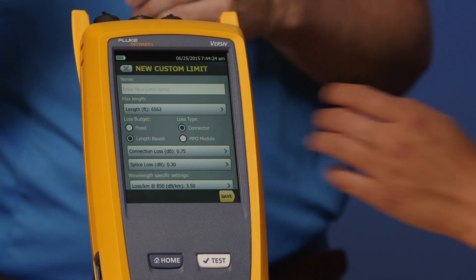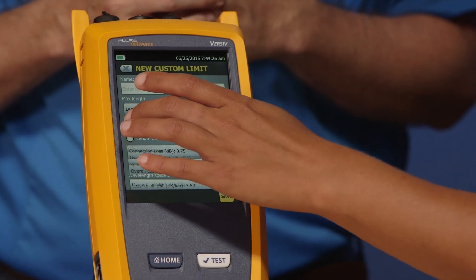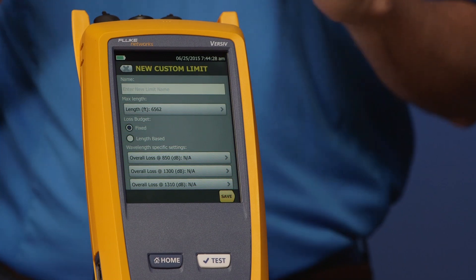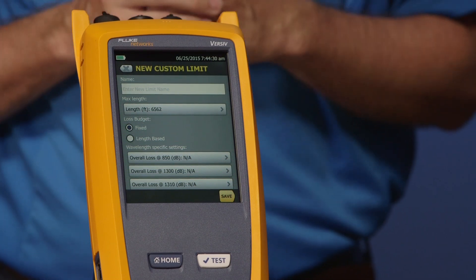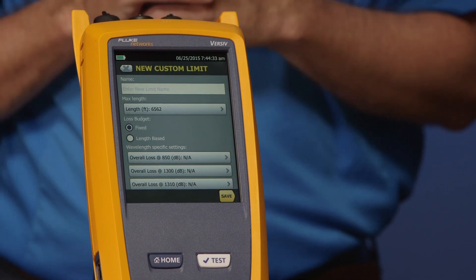When you're creating a custom test limit there are two flavors to choose from: fixed and length-based. Length-based is where you want to take something like the TIA or ISO standard and tighten up the fiber loss or cable connector requirements. You may have a situation where the consultant has already specified what the loss of that link is — just a fixed loss value — in which case you would tap Fixed Loss. Go ahead and tap Fixed Loss and you can see the screen automatically changes, then you just put your values in, but we're not going to do that today.